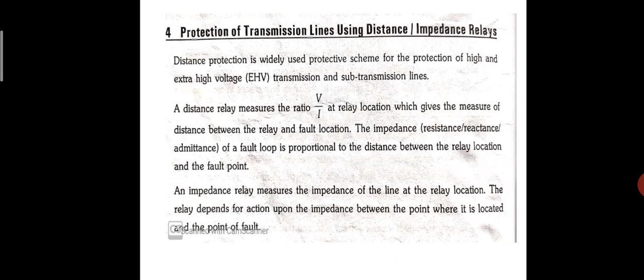An impedance relay measures the impedance of the line. At the relay location, the relay depends for action upon the impedance between the point where it is located and the point of fault. If the ratio V by I is less than Z, the impedance of the line section being protected, the relay will trip instantly. If V by I is greater than Z, it indicates that the fault is beyond the protected line and the relay will not trip.